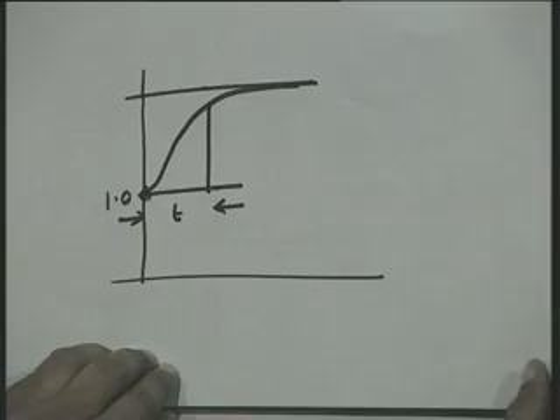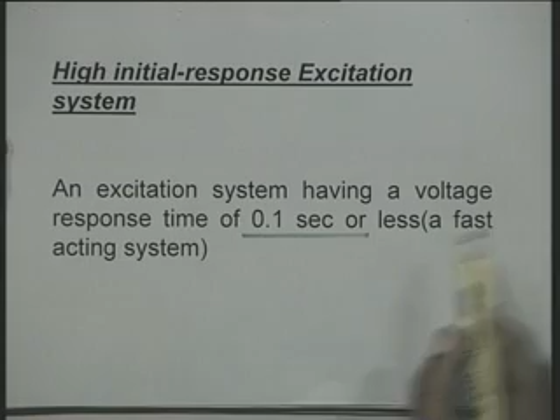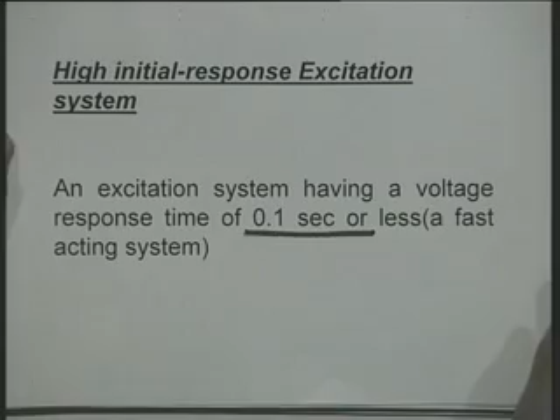Let us say this is the 95% of the difference between the ceiling voltage and the rated voltage, and this time t is the time in which the voltage will rise from the rated value and attain 95% of the difference between ceiling voltage and the rated voltage. This is the voltage response time. Now, modern excitation systems have very high response, and we specifically characterize an excitation system as a high response excitation system if its response time is 0.1 second or less. That is, you have a variety of excitation systems, and those whose response time is 0.1 second or less are characterized as high response excitation systems.